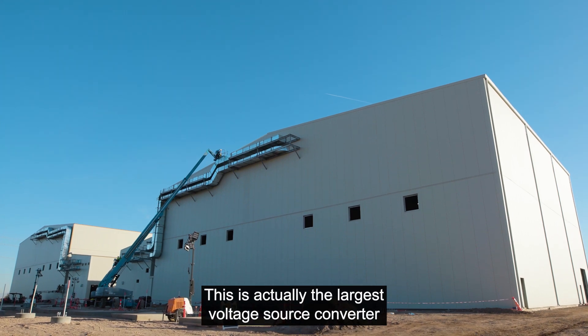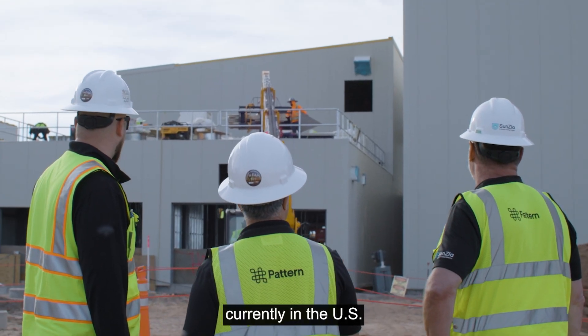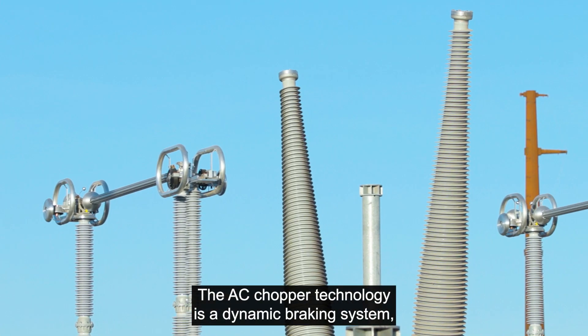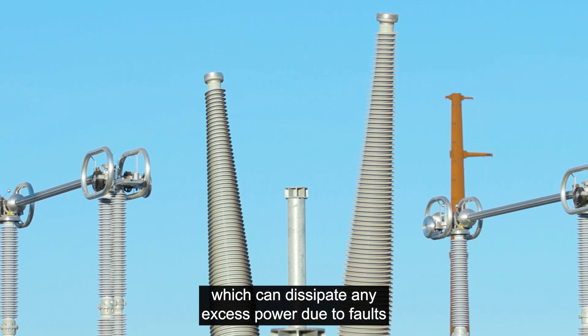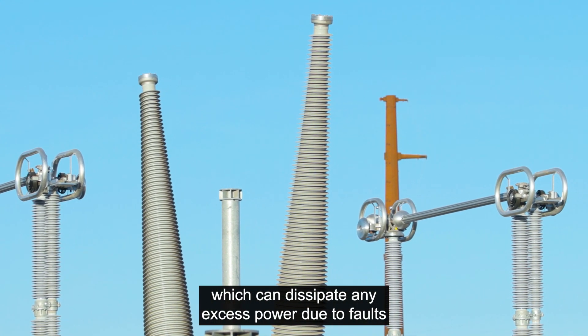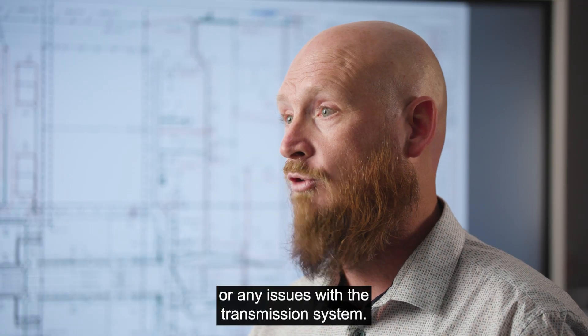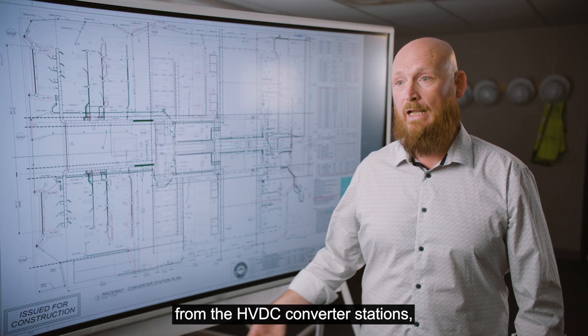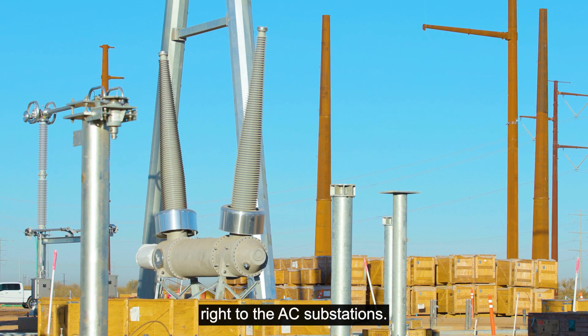This is actually the largest voltage source converter currently in the U.S. The DC chopper technology is a dynamic braking system which can dissipate any excess power due to faults or issues with the transmission system. The DC chopper will protect the complete system from the HVDC converter stations right through to the AC substations.